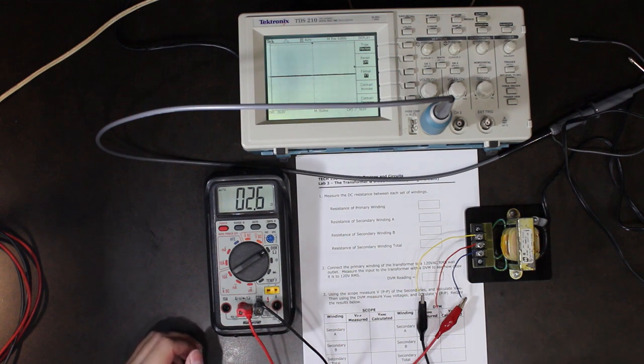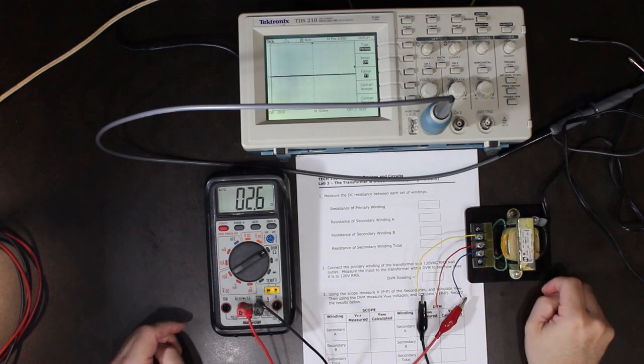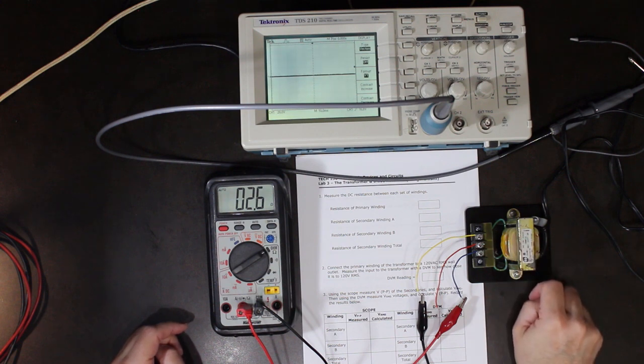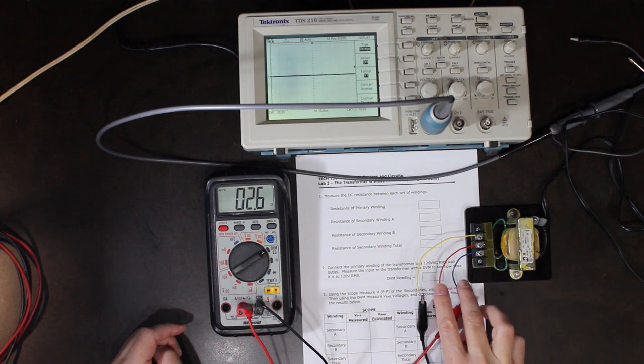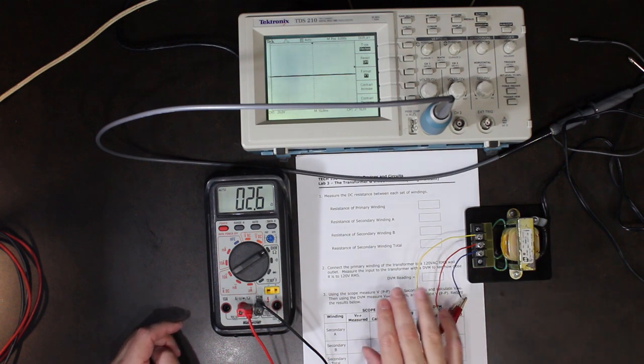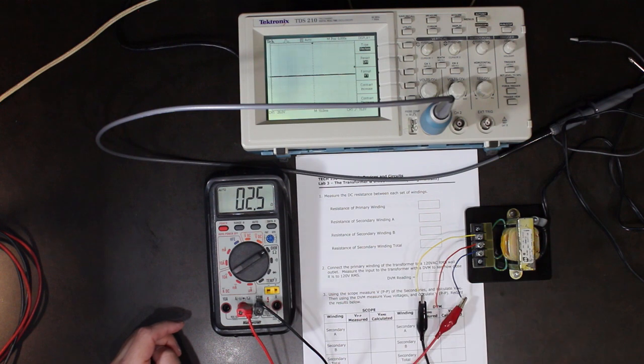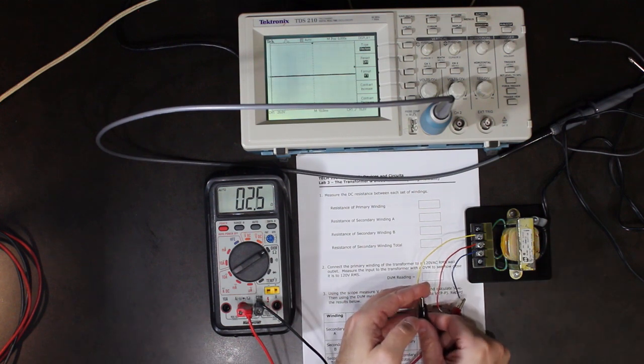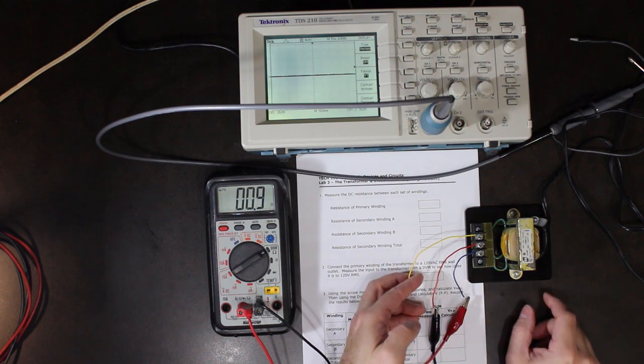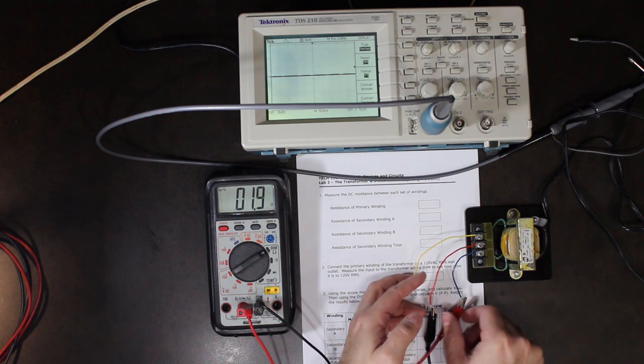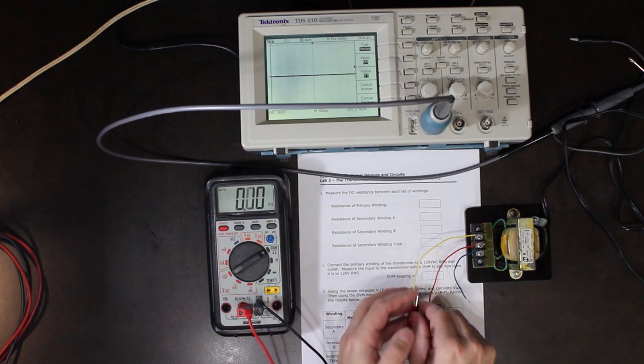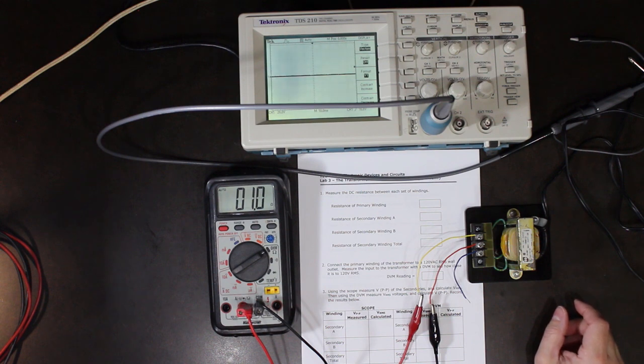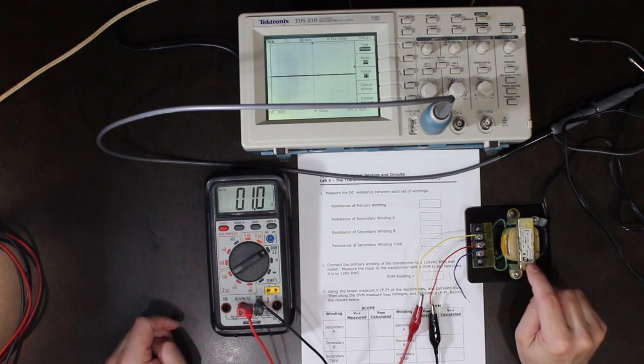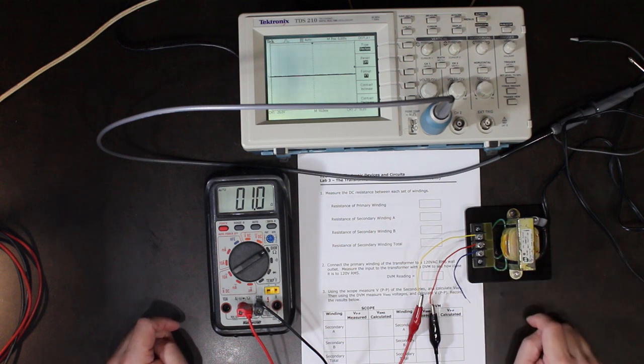What that tells me, other than that the meter is not perfectly accurate, is that this transformer has been used and abused a little bit. Winding B, from red to blue, should be identical in resistance to red to yellow. Because they are a little bit different, the resistance here is about 1.8, and the resistance here was somewhere around 1 ohm. What this tells me is that one side of the windings of this transformer has been abused a little bit.